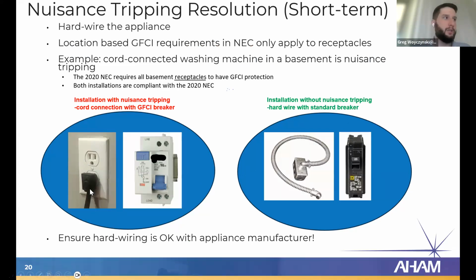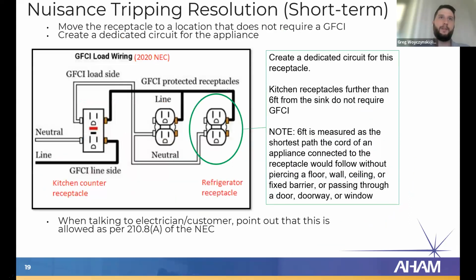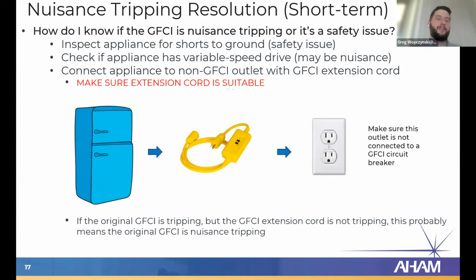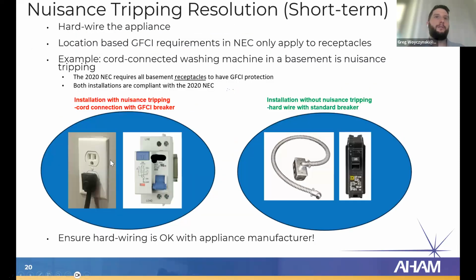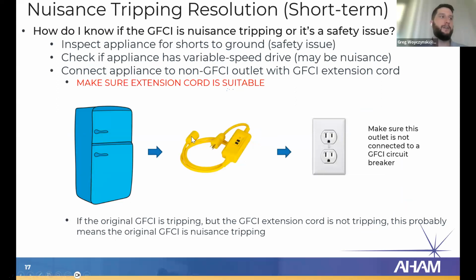The refrigerator is plugged into a receptacle, and that receptacle goes back to a GFCI circuit breaker. We know these GFCI circuit breakers can be very sensitive. They can trip on safe levels of electrical signals. So what can we do about that to see if it's nuisance tripping or not? This is one way we can diagnose it. We can unplug the refrigerator from this receptacle here. We can unplug this, and we can plug this male end into the female end of a GFCI extension cord. Then we plug the male end of the GFCI extension cord into a regular outlet that is not a GFCI outlet, and it is not connected to a GFCI circuit.